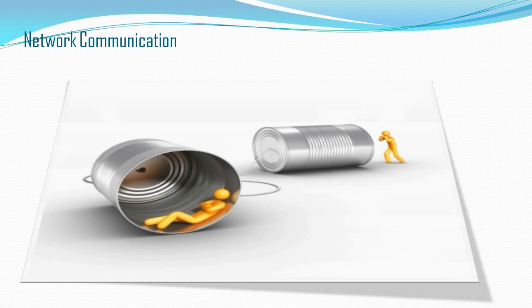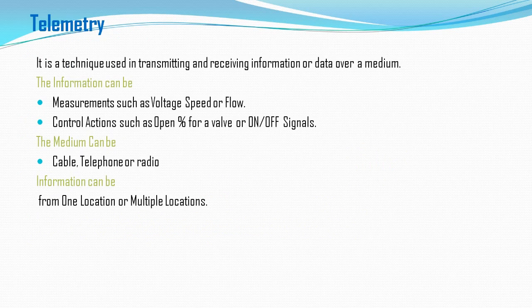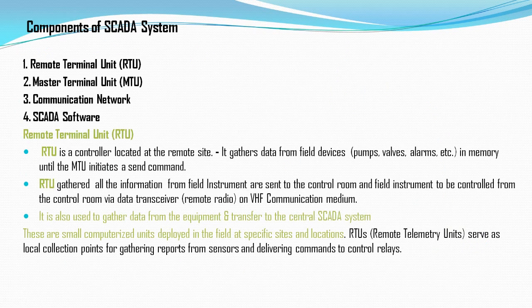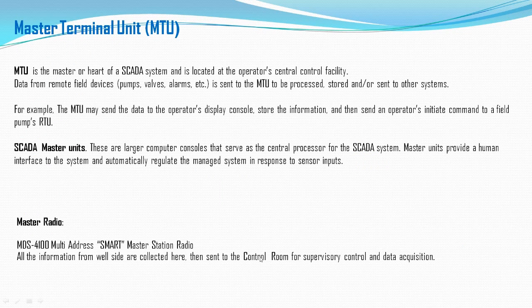The information coming from the RTU — which is the local gathering point at the remote site — goes to the master control room. Every site has an RTU, but the master control room, where the SCADA software resides, always contains an MTU. MTU stands for Master Terminal Unit and is the heart of the SCADA system, located at the operator's central control facility where all operator screens are present. Data from the remote sites is accessed through the MTU and processed there.